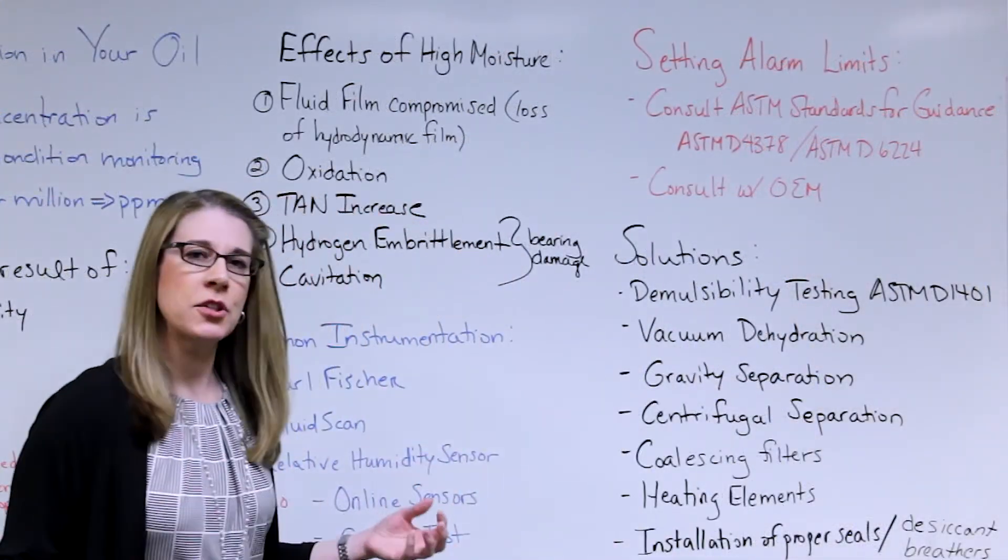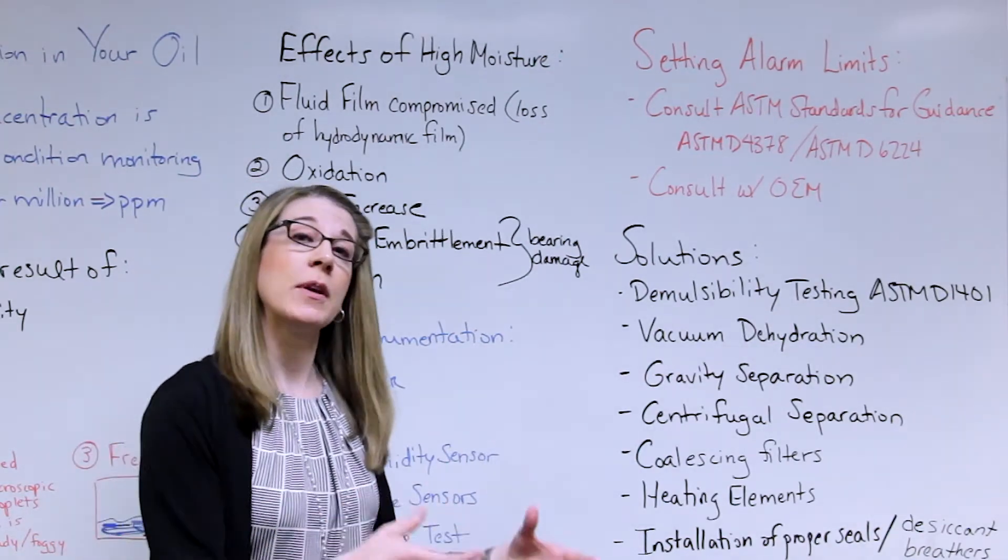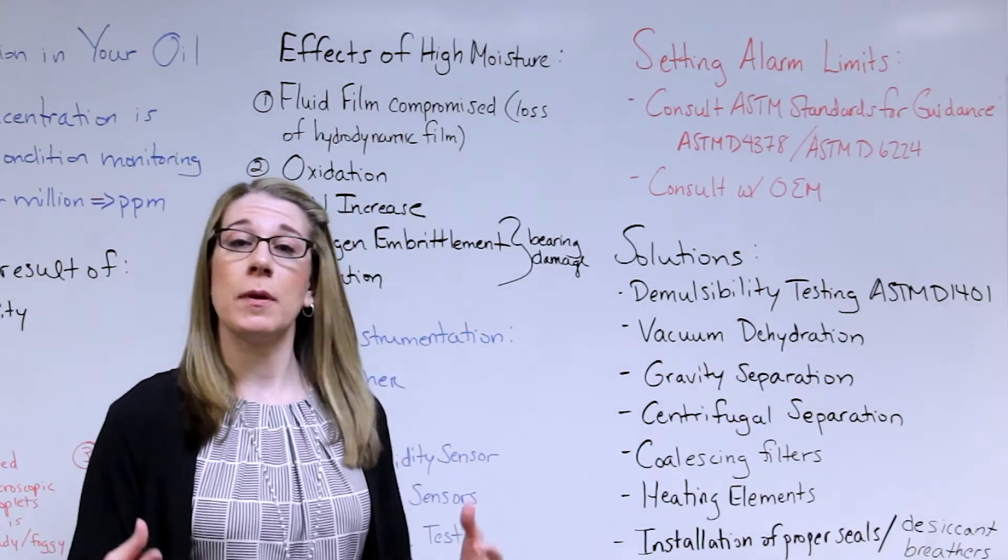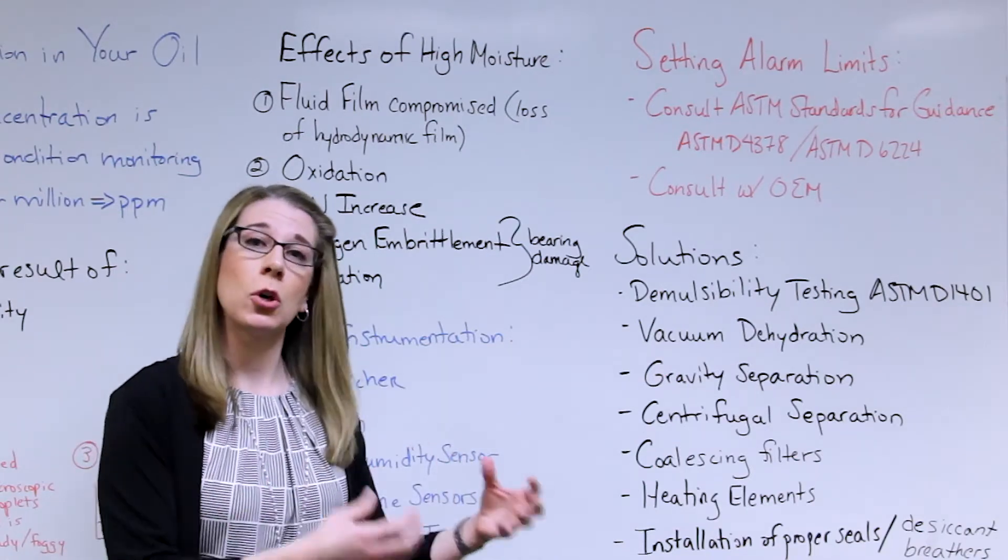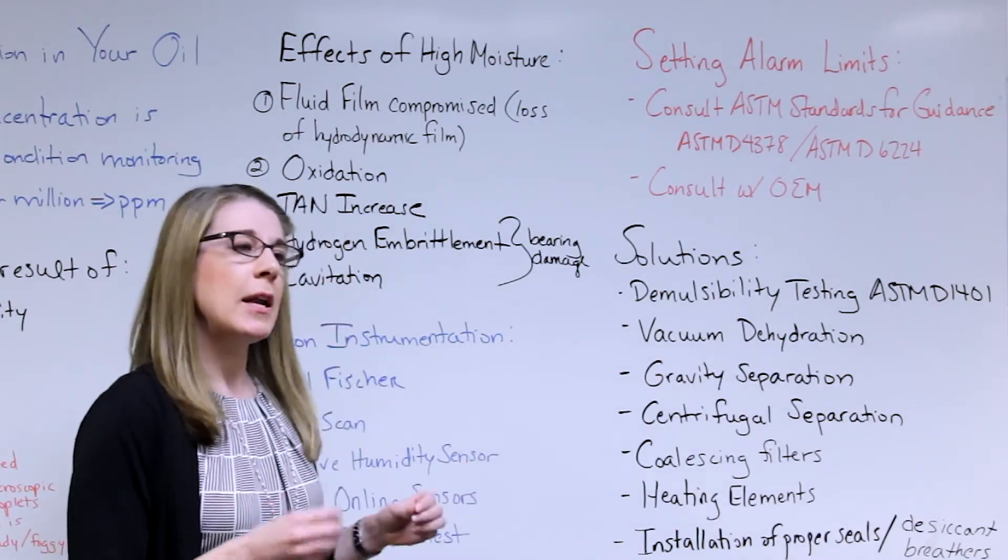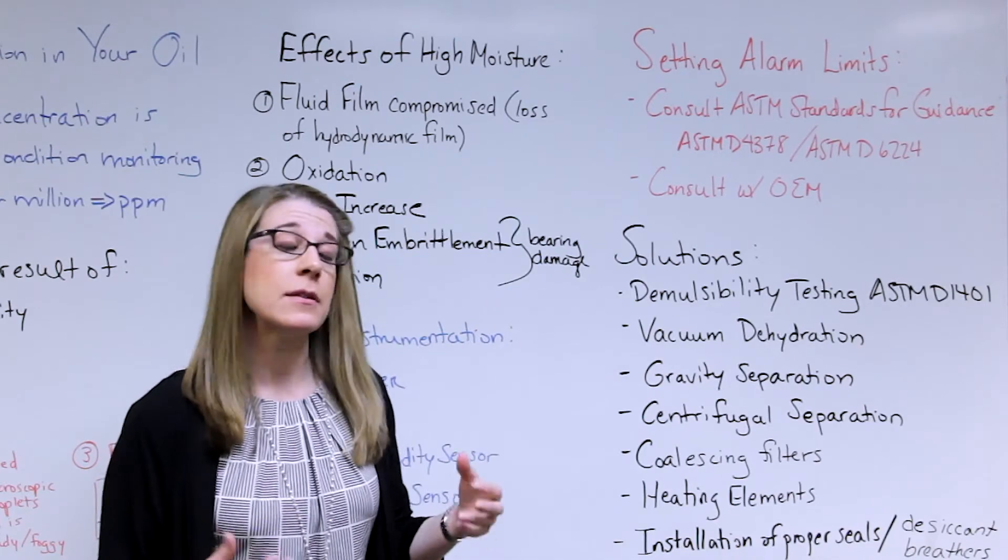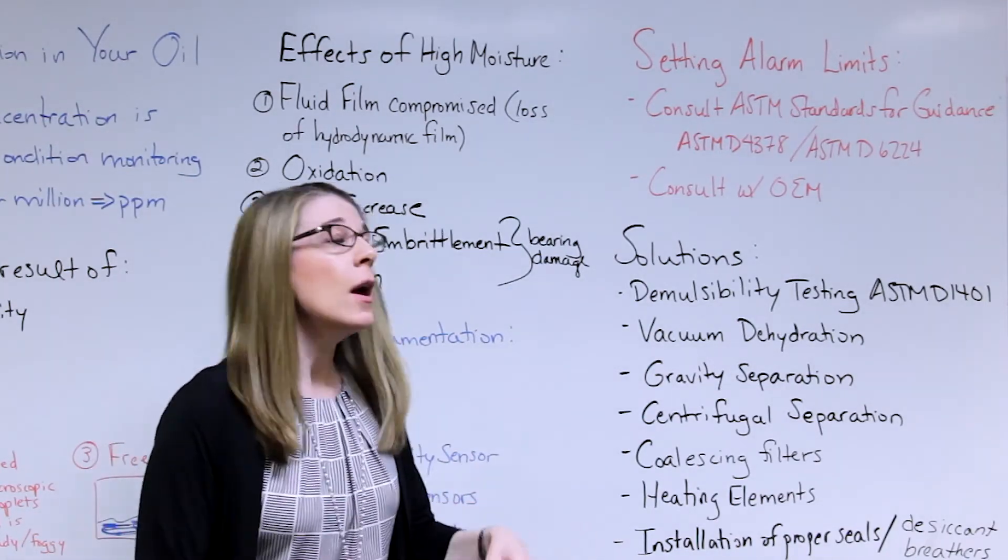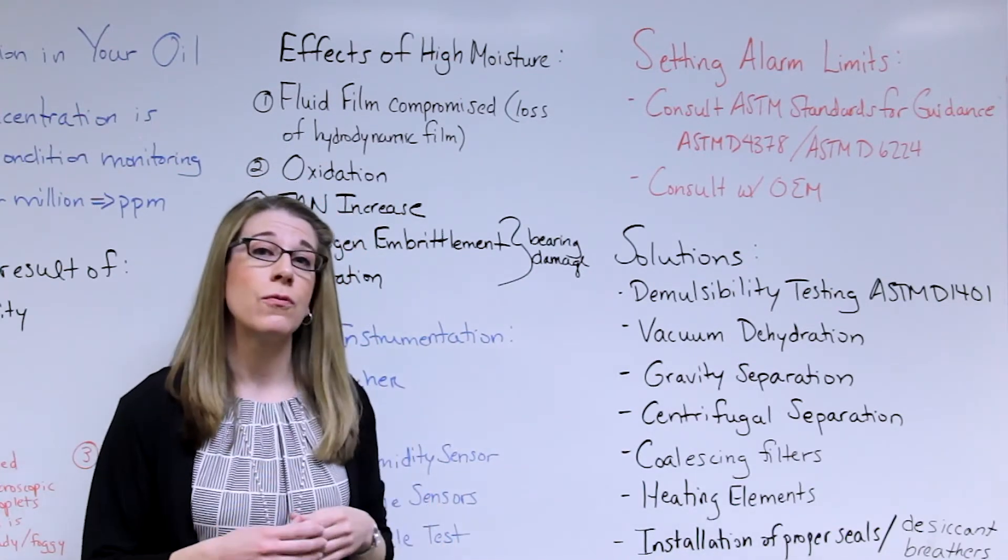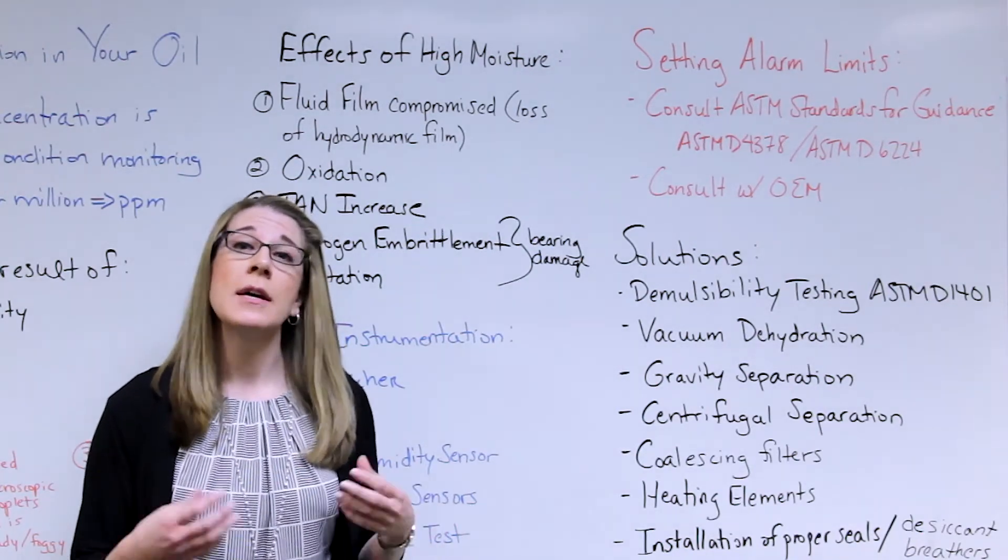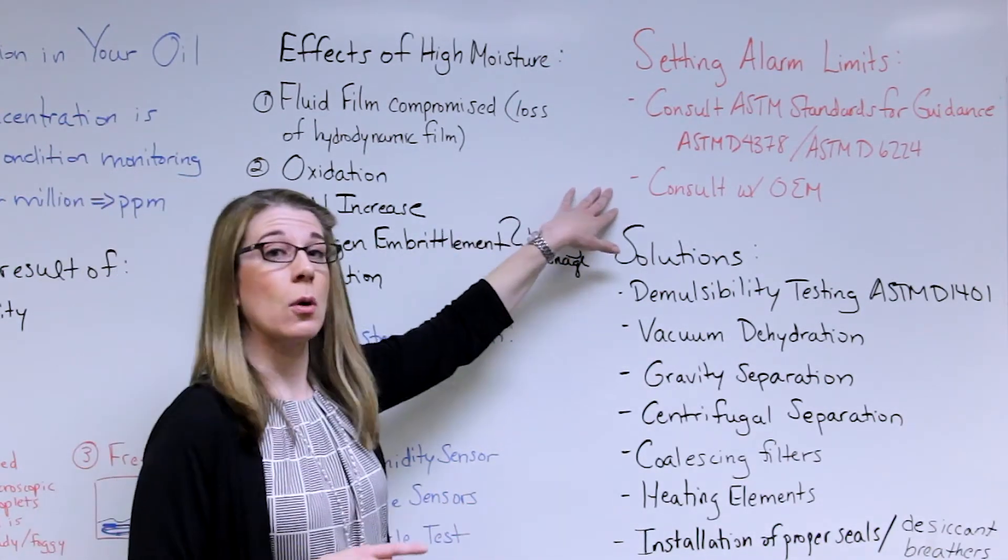Setting alarm limits is always a challenge—knowing what we're getting and what we should be getting. Specifically with turbine oils, it's going to be a little bit lower versus an engine oil, which may be a little bit higher. Keeping those things in mind is a good rule of thumb in helping us determine what those limits should be. There are also some ASTM standards out there that are really good to provide some guidance. Consulting with your OEM is great, but also familiarize yourself with these ASTM standards: ASTM 4378 and ASTM 6224. These are general practices and standards to help you set alarm limits for your oil. Good reads and worth looking at before you consult with your OEM.